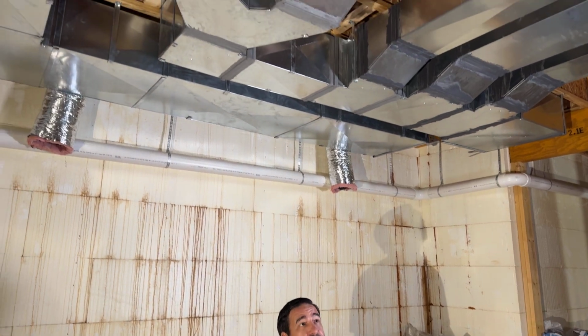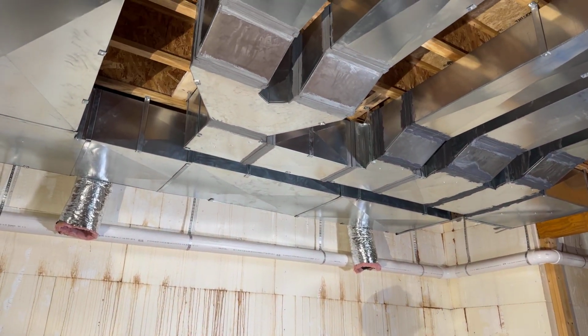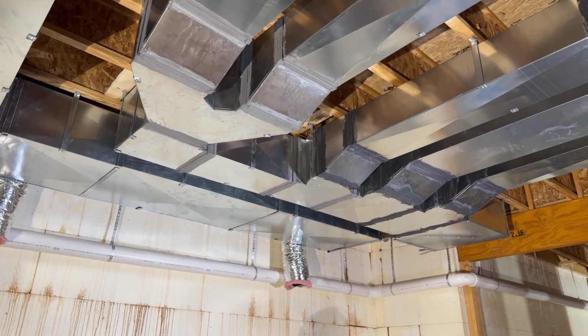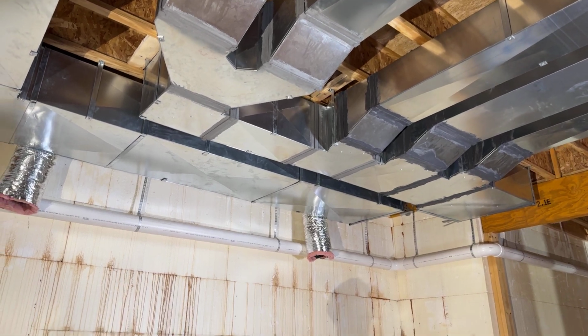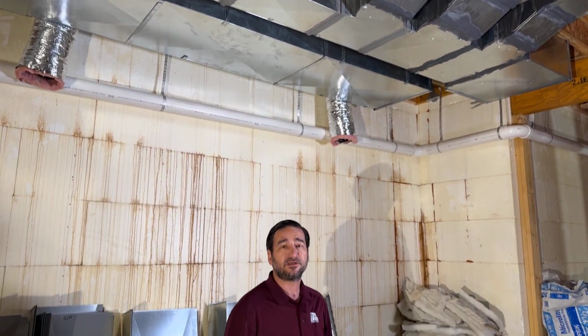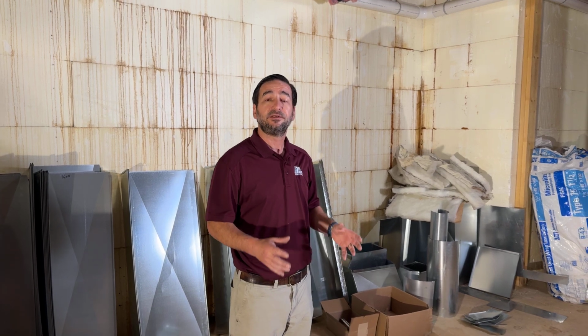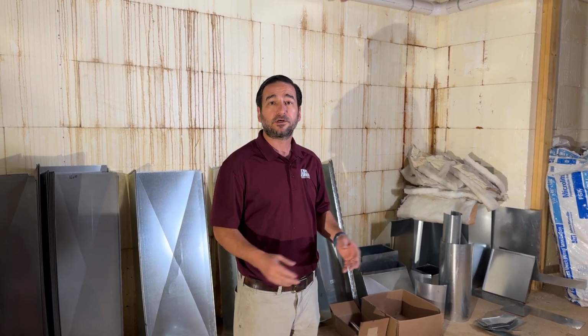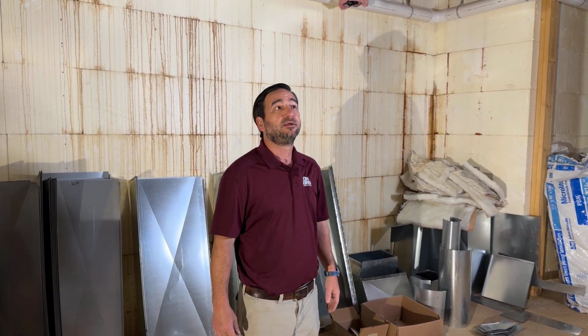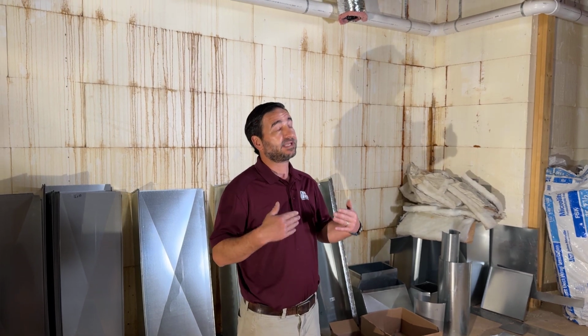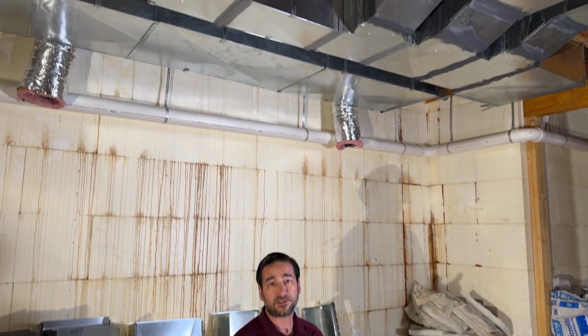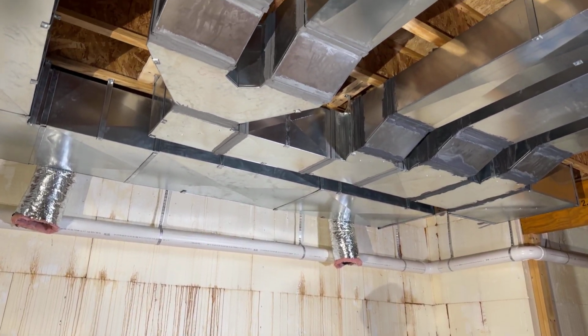So this particular house has got a geothermal system that'll have multiple zones. So there's different ways to do zoning. Most people think of a zone as an HVAC system with its own ductwork and its own equipment. Another way to zone is with mechanical zone dampers. So in this application, you use one piece of HVAC equipment.